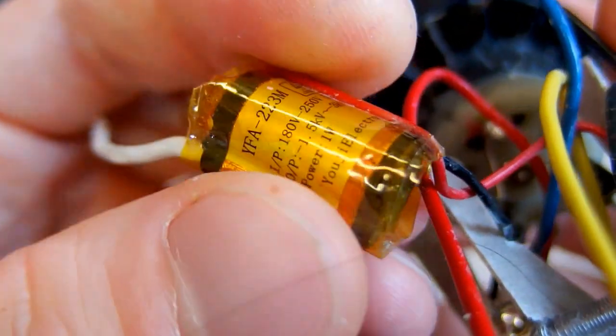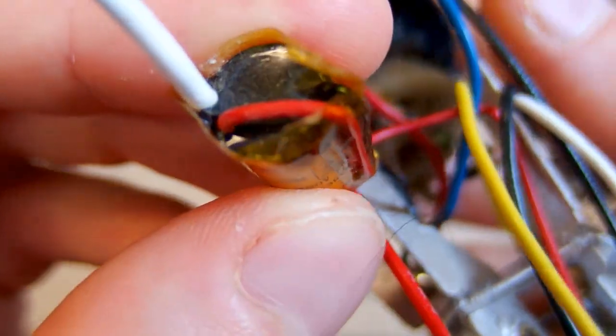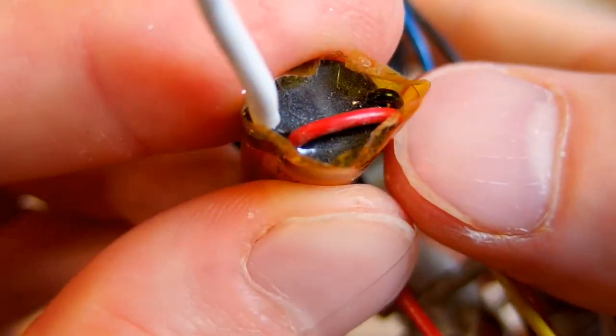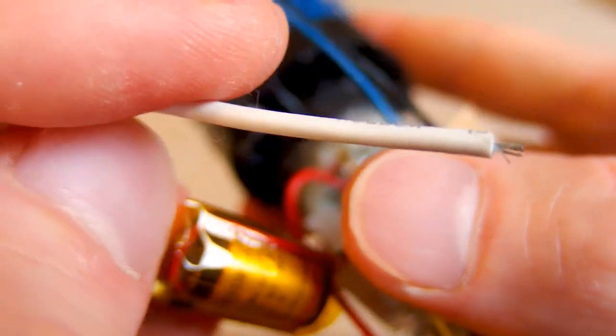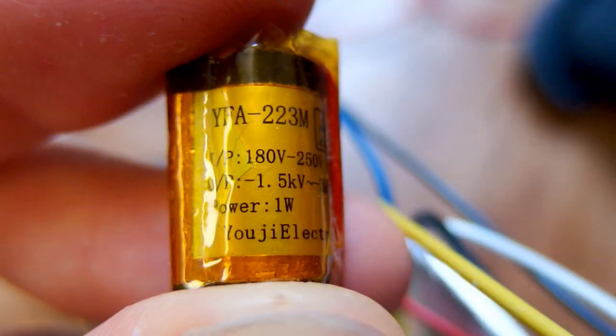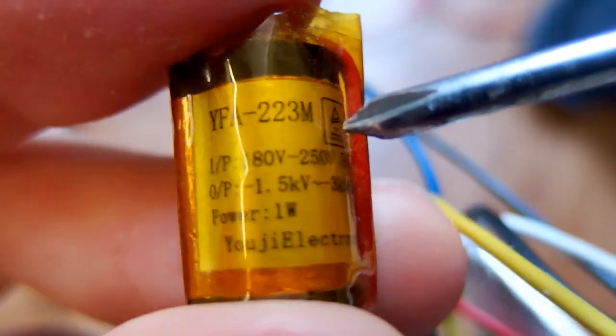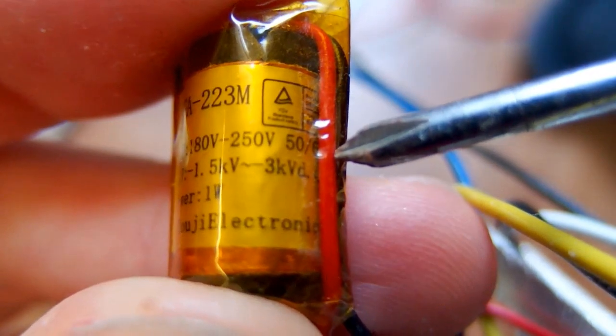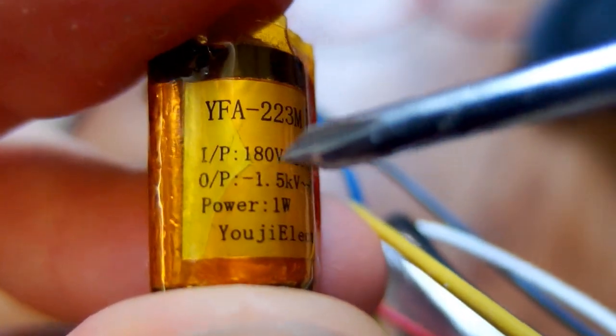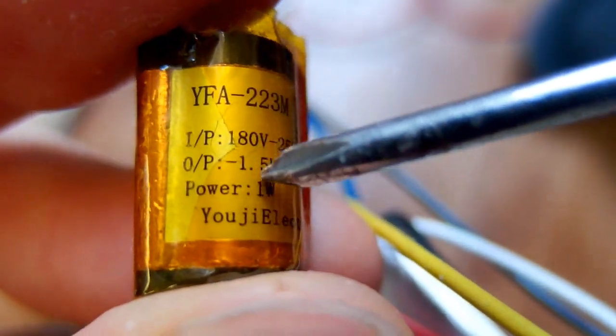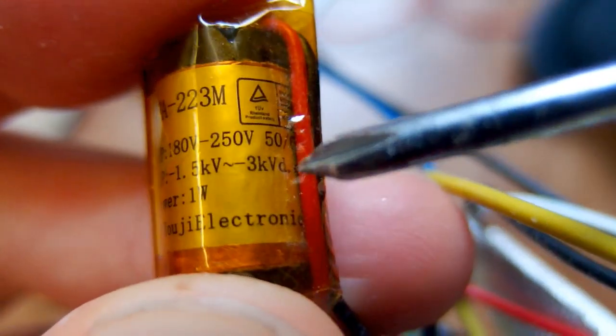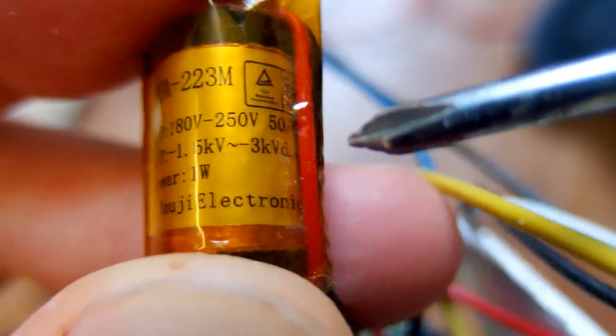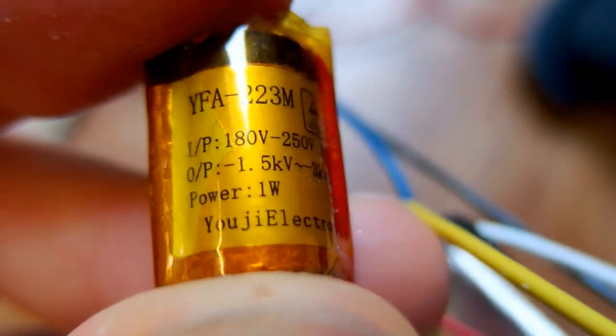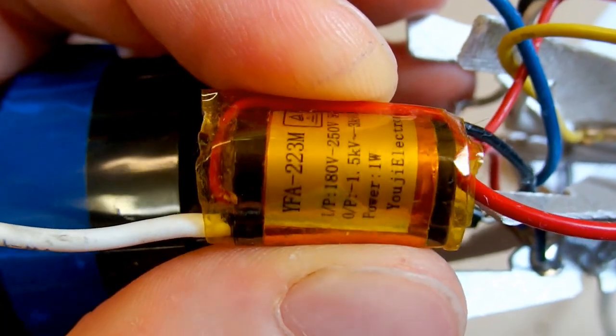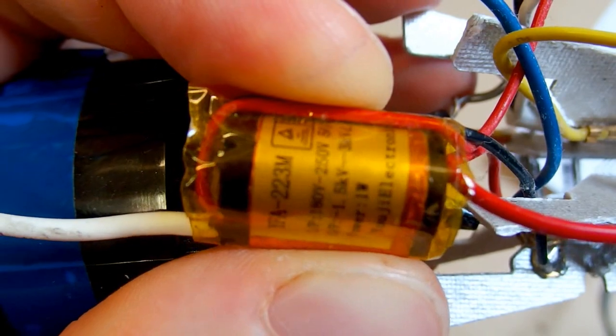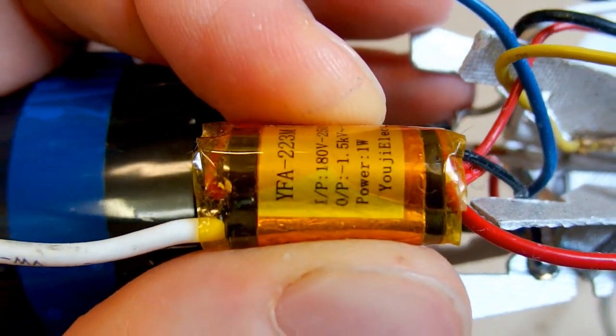It's in a plastic package filled with resin. It has 3 connections: mains coming in and the output. The input is 180 to 250 volts, 50 or 60 hertz, and the output is minus 1.5 kilovolts up to minus 3 kilovolts, with power of 1 watt. Is it a switching power supply or just a multiplier? The multiplier is much more likely.